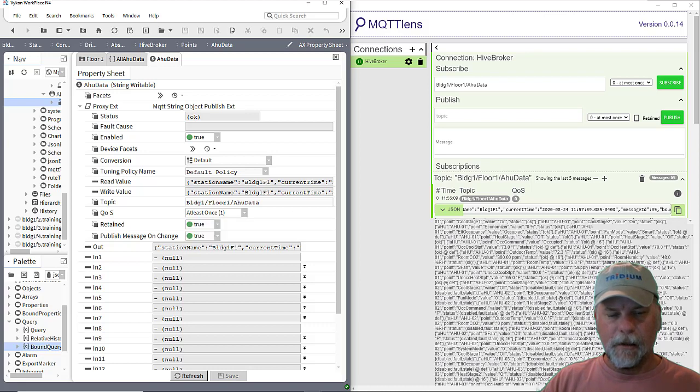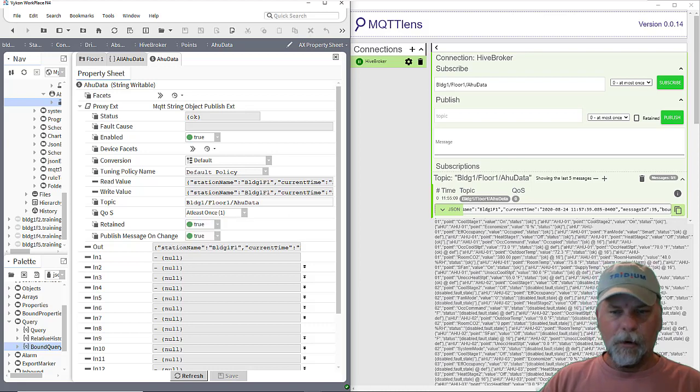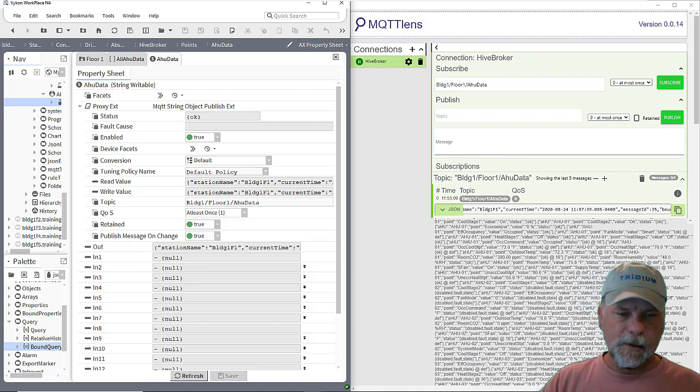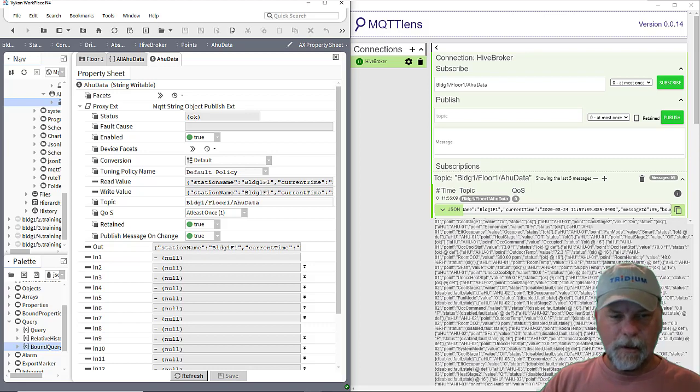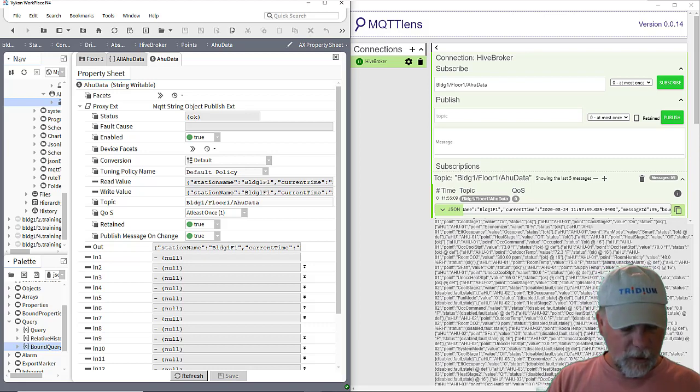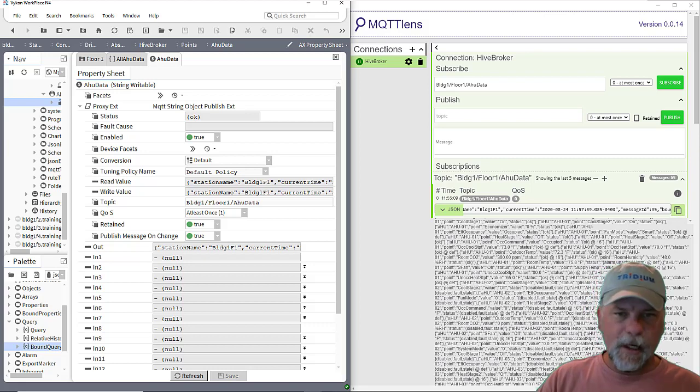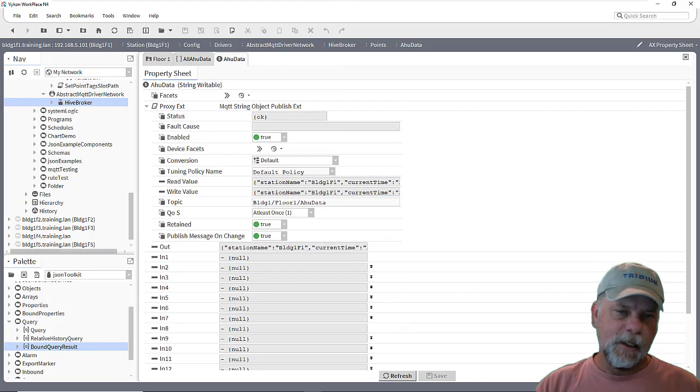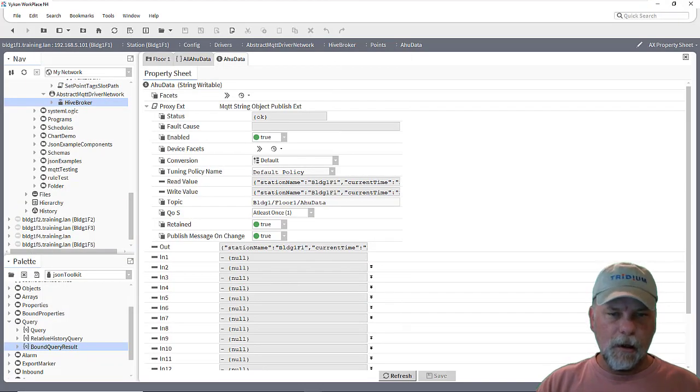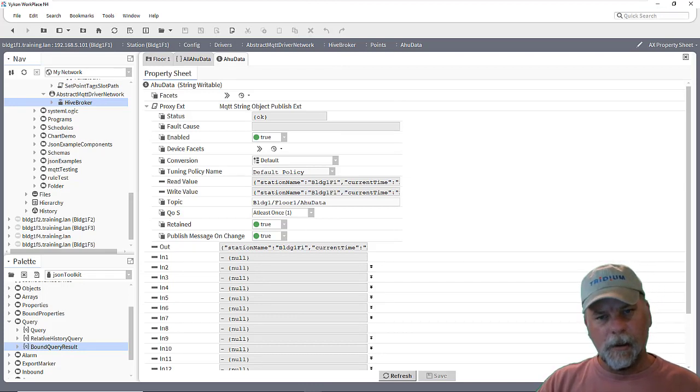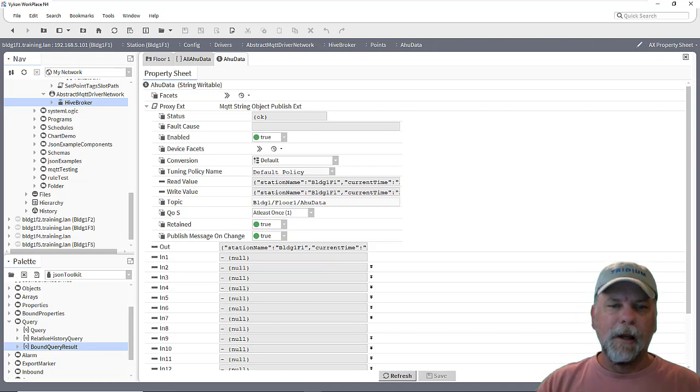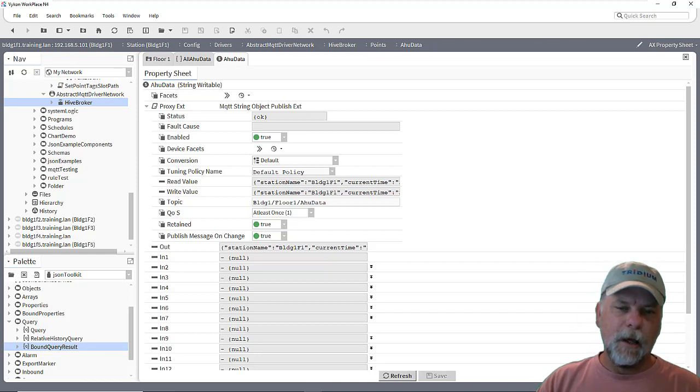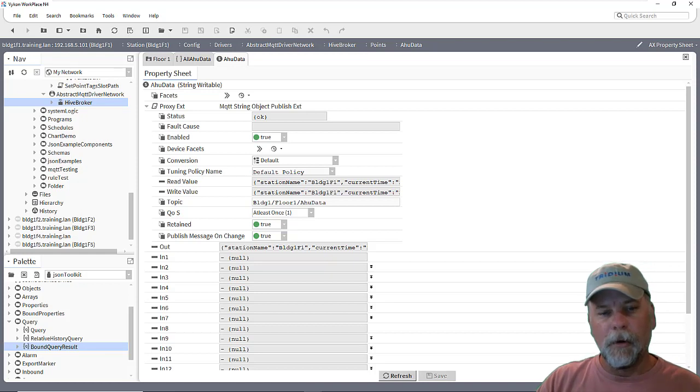then as soon as a client connects and asks for it, then the broker responds with that message because the QoS level is at one. And then I also set it to retain, which means the broker will keep a copy of that message. So that's just a real quick example of using a JSON schema to send all the AHU point data from the BACnet network as a single string published message from the station to a broker and a client able to subscribe and get that JSON payload from the broker.